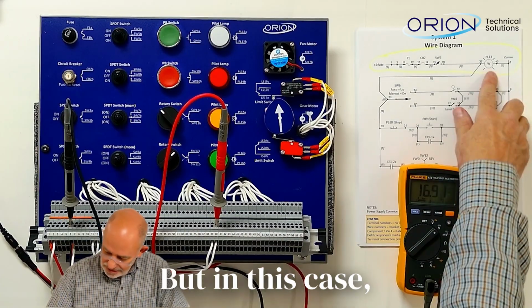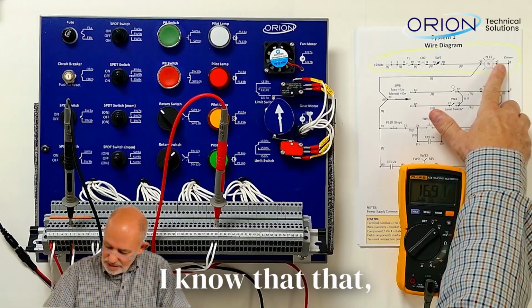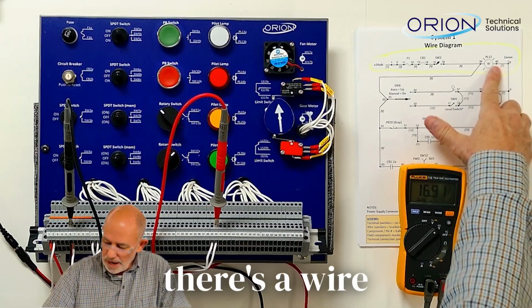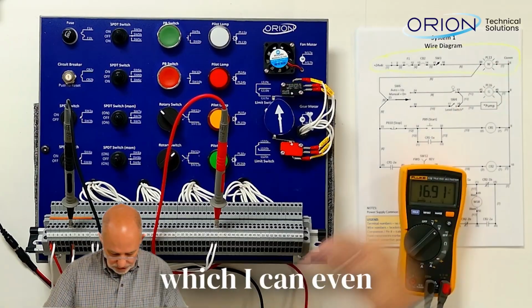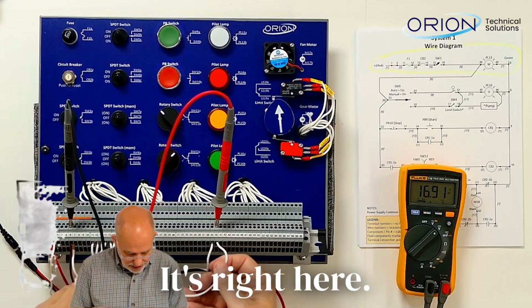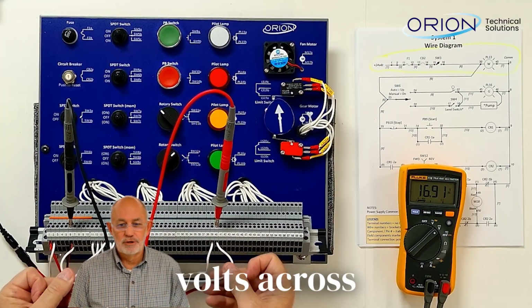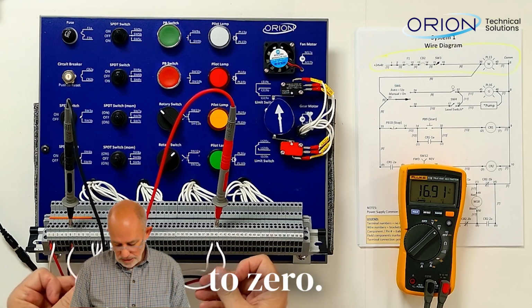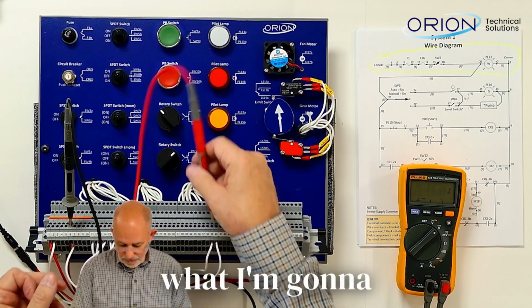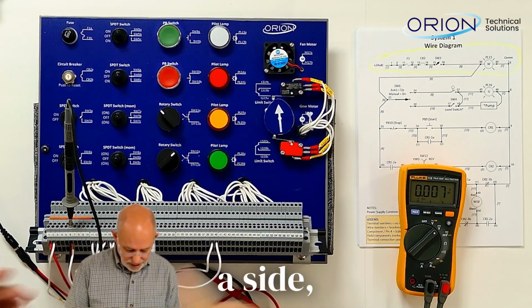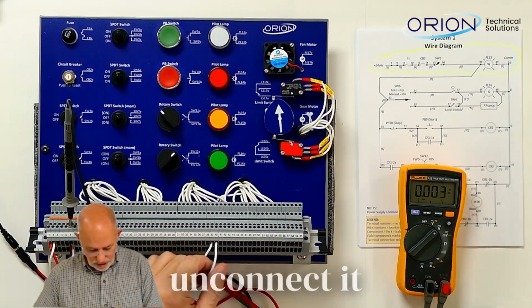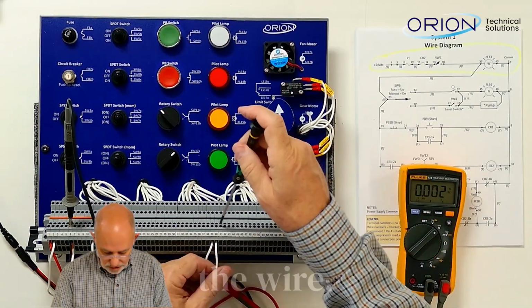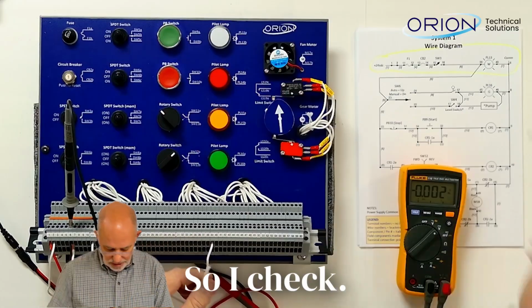But in this case, I'm going to say, well, I know that there's a wire between pin 6 and pin 40, which I can even see. It's right here, pin 6 to pin 40. That wire should have 0 volts across it, or real close to 0. So why does it have higher voltage? Well, what I'm going to do is pick a side, eeny, meeny, miny, moe, and I'm going to disconnect it to start tracing the wire. So I check. Oh, look at that.